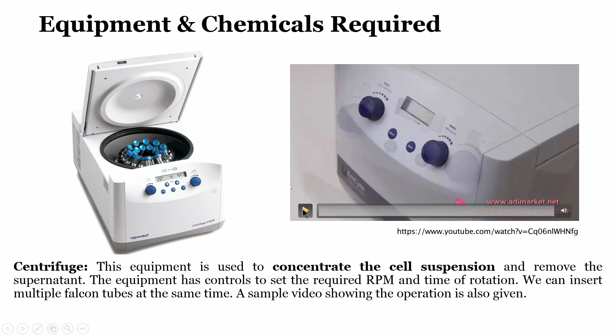All right. So, the equipment is used to concentrate the cell suspension and remove the supernatant. The equipment has controls to set the required RPM and time of rotation. Depending on how fast you rotate and how much time you take for rotation, we can separate the suspension from the cells. We can insert multiple Falcon tubes. These are called Falcon tubes, and you can see there is an array of Falcon tubes right over here. At the same time, a sample video showing the operation is shown right over here. So, let us see how the centrifuge works in real time, and then we continue to the next slide.